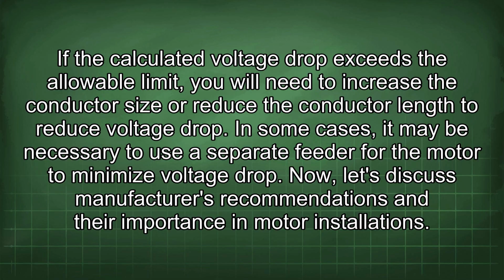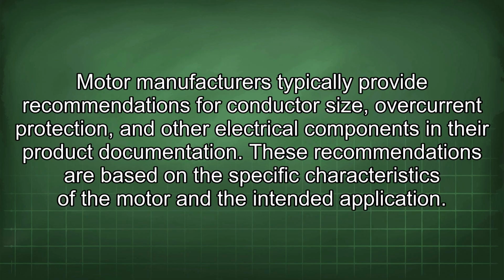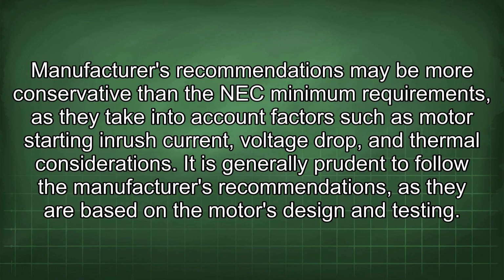Now let's discuss manufacturers' recommendations and their importance in motor installations. Motor manufacturers typically provide recommendations for conductor size, overcurrent protection, and other electrical components in their product documentation. These recommendations are based on the specific characteristics of the motor and the intended application. Manufacturers' recommendations may be more conservative than the NEC minimum requirements, as they take into account factors such as motor starting inrush current, voltage drop, and thermal considerations. It is generally prudent to follow the manufacturer's recommendations, as they are based on the motor's design and testing.